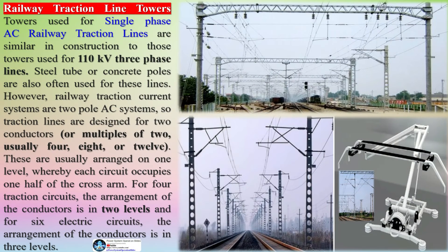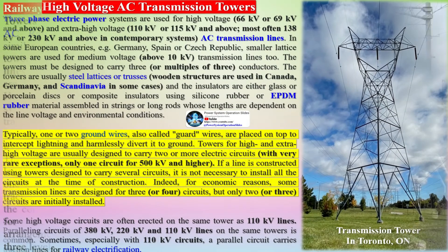Towers used for single-phase AC railway traction lines are similar in construction to those used for 110 kV three-phase lines. Steel tube or concrete poles are also often used for these lines. However, railway traction current systems are two-pole AC systems, so traction lines are designed for two conductors or multiples of two — usually four, eight, or twelve.